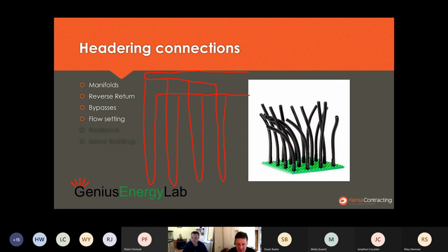So what you're looking at here is when you're actually trying to flush the system out, if you keep all of this pipe along here the same size, say 63 mil with 4 boreholes, then you're trying to put all of the dirt, all of the air and everything else that's in this bit of the pipe down 40 mil borehole. So you're trying to squeeze 63 mil worth of dirt and so on down into a 40 mil borehole, which actually makes your flushing and purging very difficult.